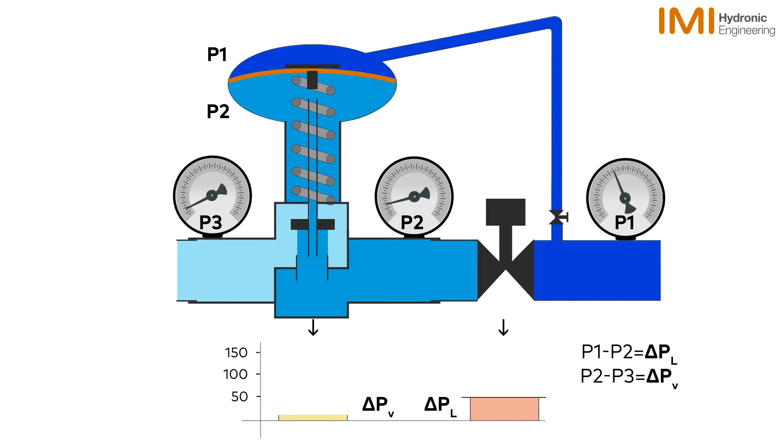As P1 increases, delta PL will initially increase proportionally. The valve then sees this change and acts to close down proportionally, thus decreasing delta PL to set point and increasing delta PV in proportion.